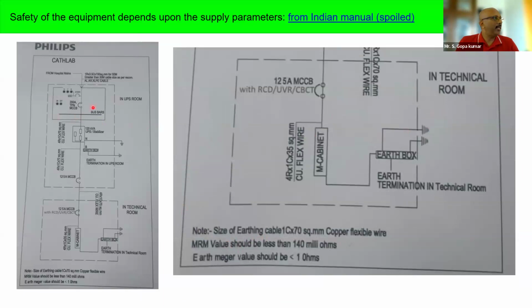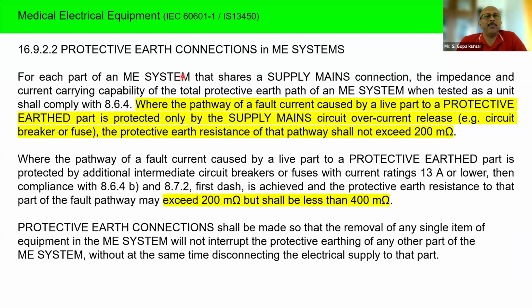This manual says there is a UPS, and the UPS you can see here neutral to separate earth pit. Then there is an earth box, and somewhere they have put, as you can see here, the earth measure should be less than 1 ohm. We had a chat discussion with the engineers from the manufacturer. What they say is there are 4 earth electrodes, connection to 4 earth electrodes are required, and each of these earth electrodes should have a resistance of less than 1 ohm. So basically, they are totally violating the fundamentals of electrical safety, violating the fundamentals of the recommendation of their own standard. For example, these medical equipments are made based on the standard IEC 60601 Part 1.